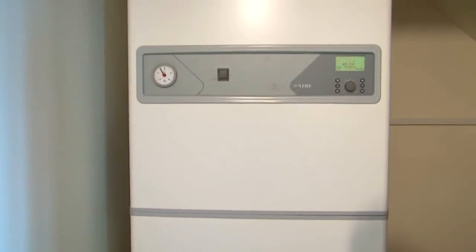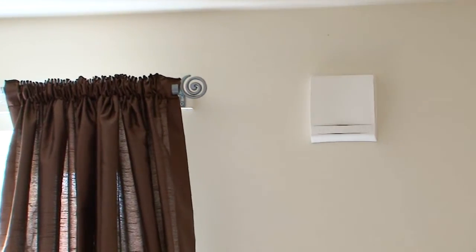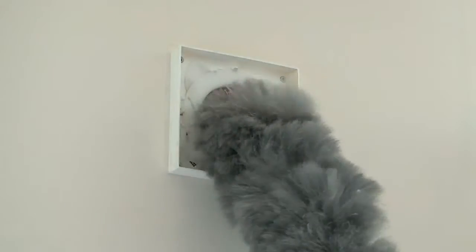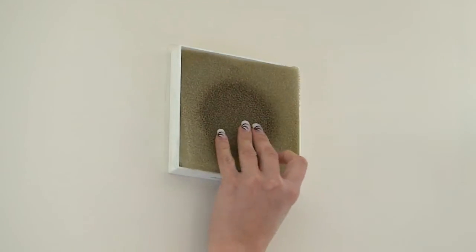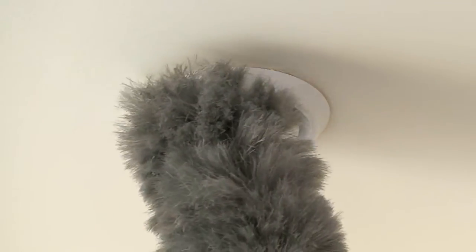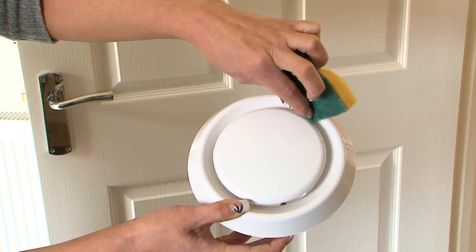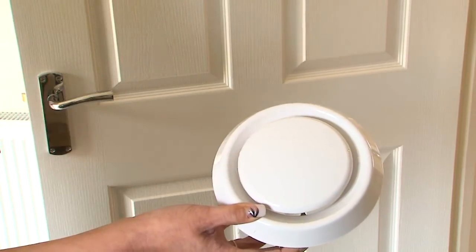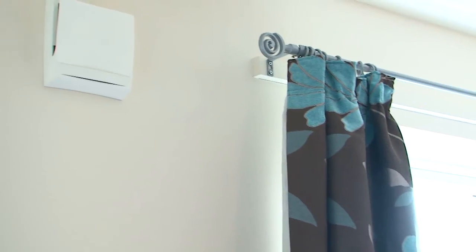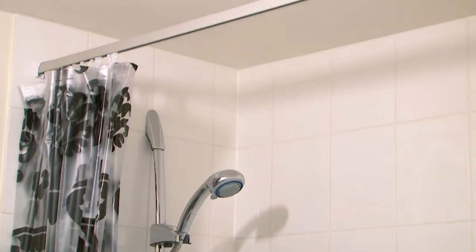Although your heat pump requires very little maintenance, we do advise that once a month you check that all the ventilation ducts are free of dust and are not blocked in any way. If you need to clean any of the ventilation units, simply use a duster to clean the surface or remove the unit covers to wash and clean them more thoroughly before replacing them back into their housings. Depending on your system you will have one or two vents bringing clean air in from the outside and three to four internal vents mounted in the ceiling in different rooms. These vents are an essential part of your heating system and circulate air through the heat pump and around your property. To make sure that the correct ceiling vents stay in the correct rooms, clean each vent separately to avoid mixing them up. It is also essential that the settings of the individual vents are not tampered with or swapped between rooms, as these have been preset and balanced by the installer for them to work to their best efficiency.